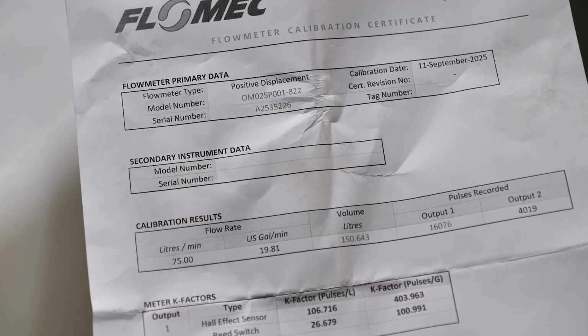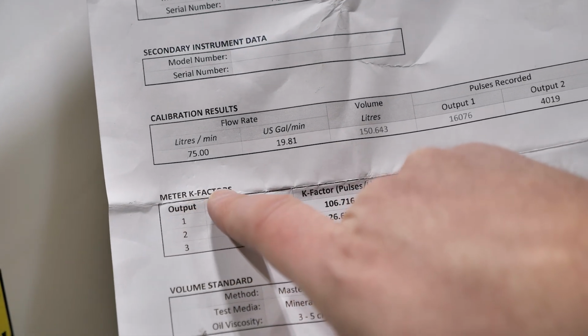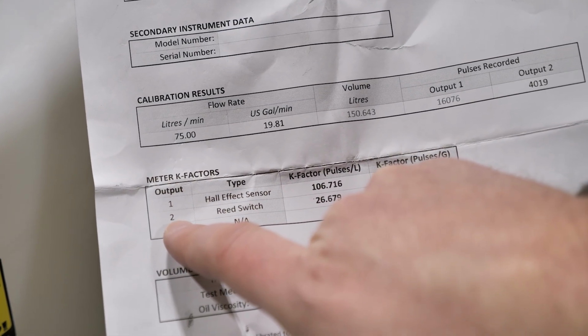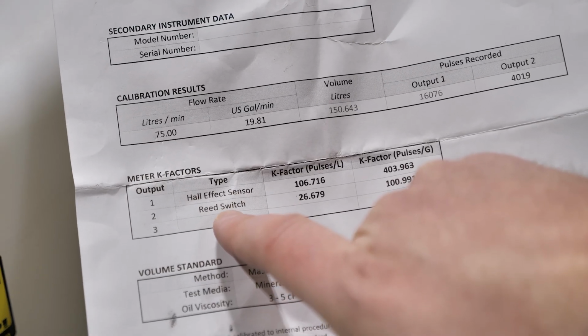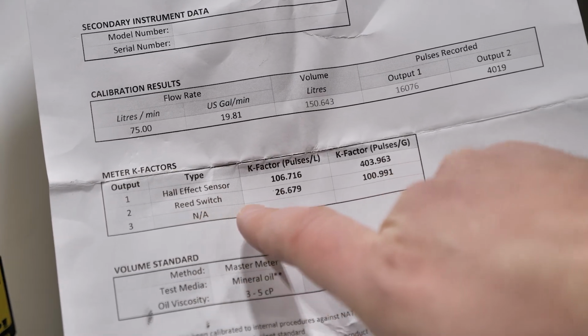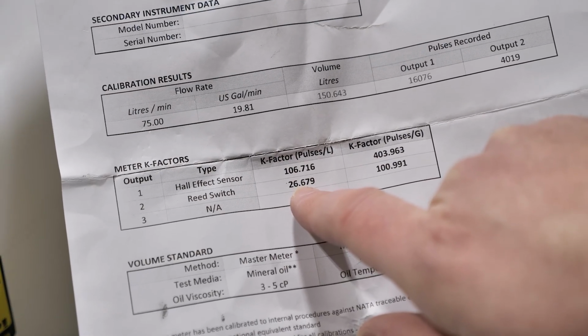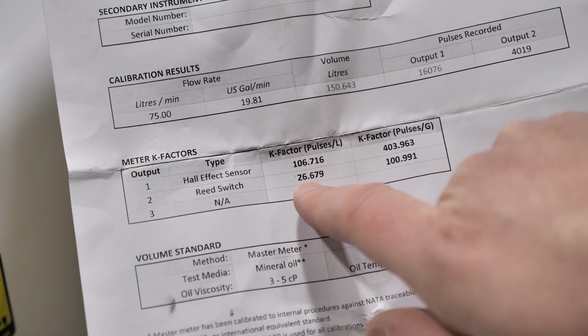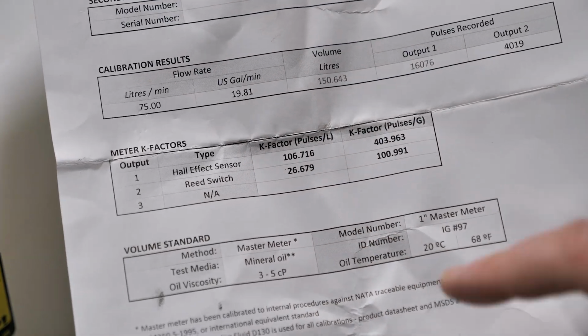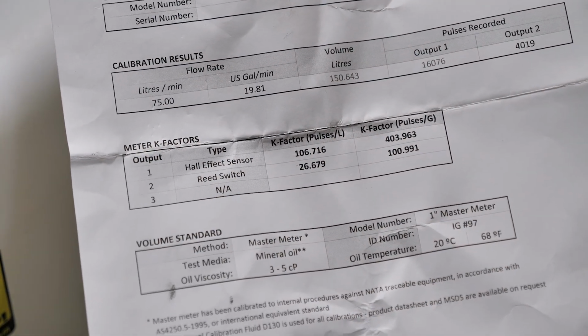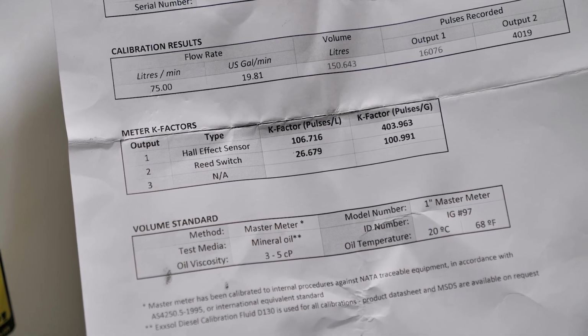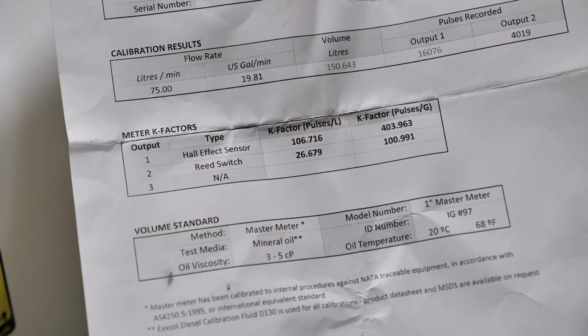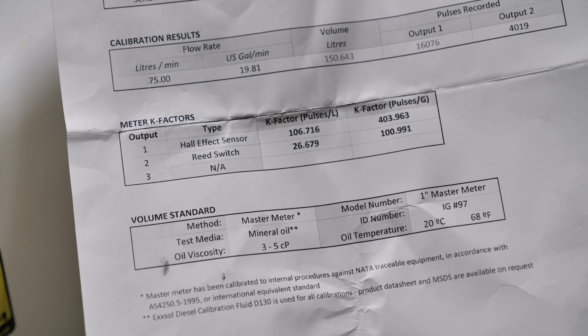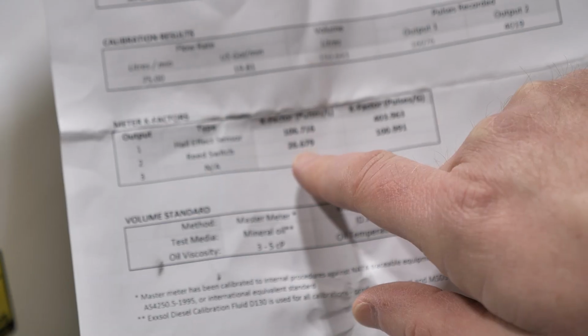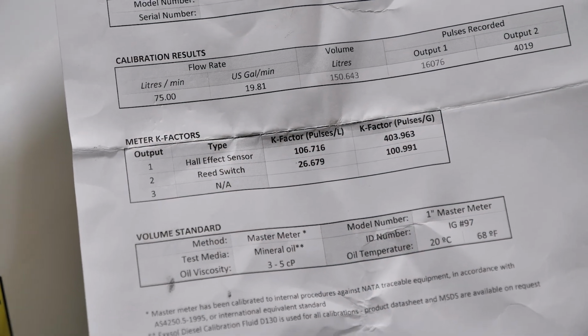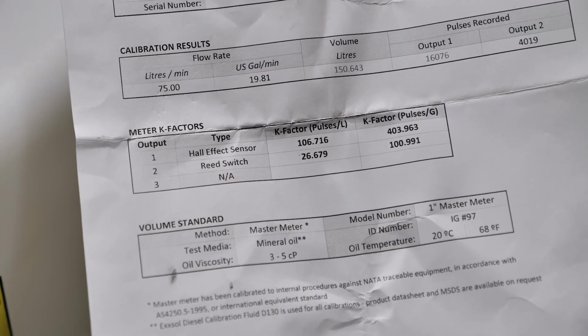And the critical information on here is this meter K factor. And if you remember, we had our display set to reed switch. And the critical factor is this pulses per liter. And for us, it is 26.679. You'll also notice it is in pulses per liter. I know we changed our setting over to gallons, but you do not have to change how you put in that K factor. You always want to put in K factor in pulses per liter. It's very critical that it is in pulses per liter. So I want to stress that very much.